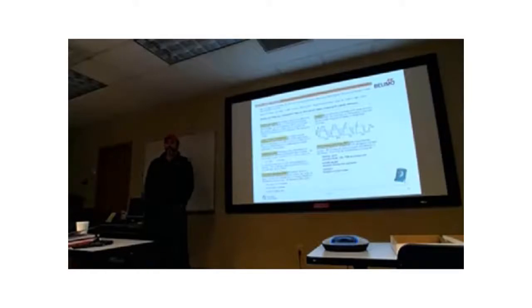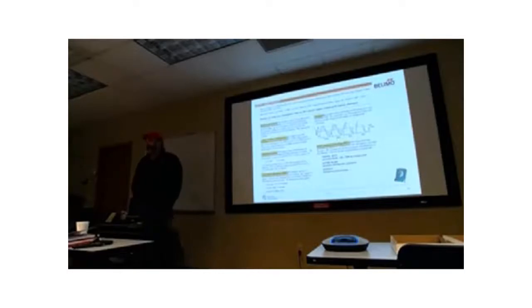On off. Floating point is, well, who can describe floating point to me? What is a floating point signal? How do you get it done in the field? I can see those of you that took the course didn't take. Well, let's just use something that we've learned, supposedly. What kind of outputs are required to operate a floating point actuator? You need two digital outputs to run a floating point control.